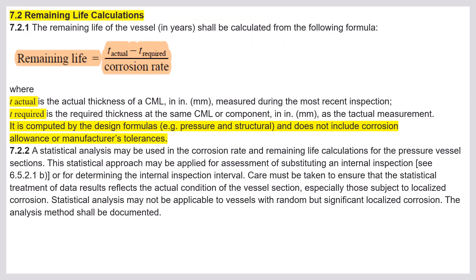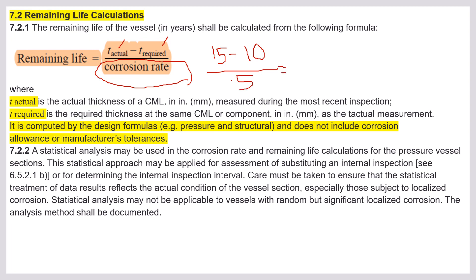For remaining life calculations, once you get the corrosion rate, the remaining life formula is: (t_actual − t_required) / corrosion rate. For example, if t_actual = 15 mm, t_required = 10 mm, and corrosion rate = 0.5 mm/year, then remaining life = (15 − 10) / 0.5 = 5 / 0.5 = 10 years. So the remaining life is 10 years.